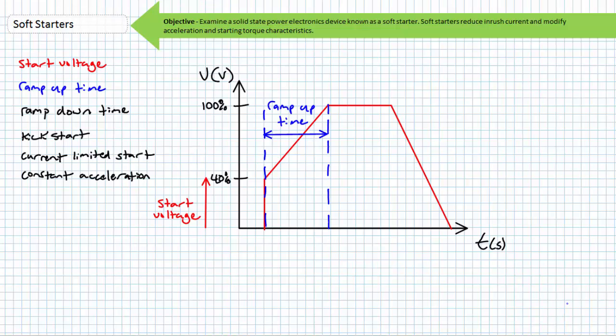The ramp-up time is the period of time it takes for the soft starter to steplessly increase the voltage from the starting voltage to full voltage. The smooth, gradual nature of the applied voltage during the ramp-up time means there is no large current surge or sudden acceleration when the motor is first started.